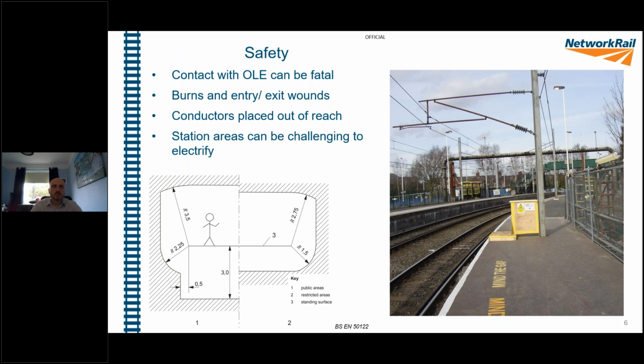The one reason for us working with 3.5 metres here is that the public themselves are, of course, unknowing of the risks of electricity, so we have to give them a greater clearance. But also we've got to consider other factors, such as the fact that they may be carrying something such as an umbrella, which reduces their distance to the live equipment. Other cases may be next to footbridges, for example, where we've got to, again, maintain that clearance, in this case, a 2.25 metre distance to said equipment.